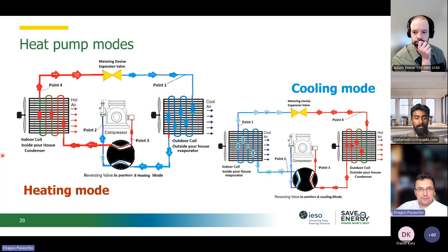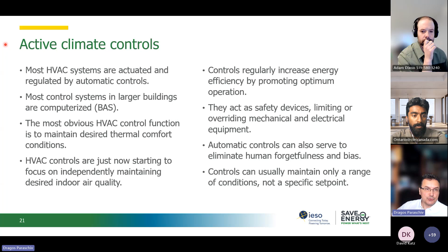We can modulate these systems that, keep in mind, were designed for the worst case scenario but then operated at part load. That's basically true as well with the heat pump. If you want to use your heat pump in the dead of winter when the temperature is very, very cold outside, in most cases in Ontario you will find a heat pump can serve you completely, but you will have to size it quite large. So controls will help us optimize this.